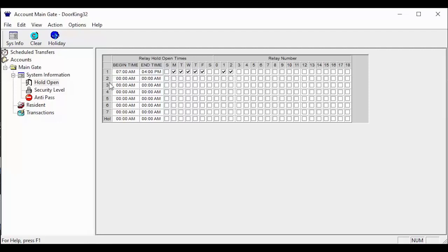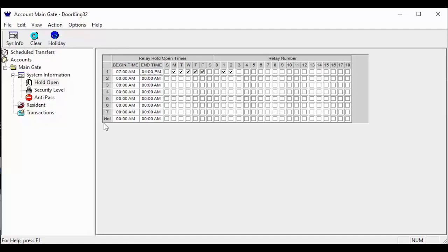The holiday schedule will affect all seven of the programmable hold schedules. The hold open screen is also where we set up the holiday times. The holiday times are the bottom schedule here denoted by HOL. Typically the holiday schedule times and days are left blank, which will cause your normal hold open schedules to do nothing on the holidays you have added under your holiday tab.